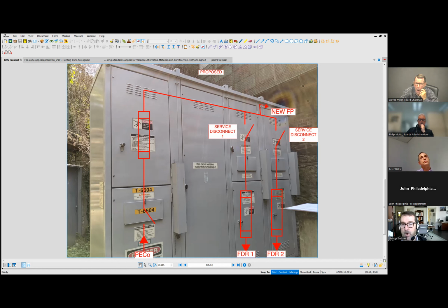A new electric fire pump has been installed in the basement and is awaiting an electrical service connection. That's not a repair, that's a new installation. Well, it's a replacement of an old fire pump. Yeah, but if we have new switch gear, we're doing a level 2 alteration and a new fire pump. It would be customary to put in a legal fire pump service ahead of the switch, the main service disconnect.